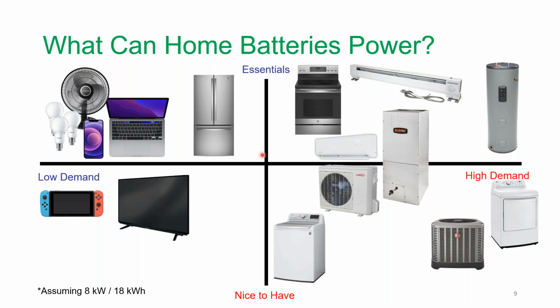What they're going to pretty much always want to do when you're installing the battery is have a critical loads panel. This is what you do when you install a backup generator in any case, but it's going to take these loads, whether it be the circuit your kitchen is on, or your boiler startup and pumps, your well pump, a couple of lights, a couple of outlets. You're going to want to put those all on one critical loads circuit breaker panel, and have your battery system just power that panel in the event of an outage.